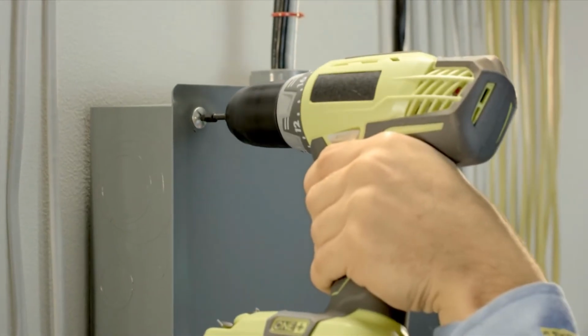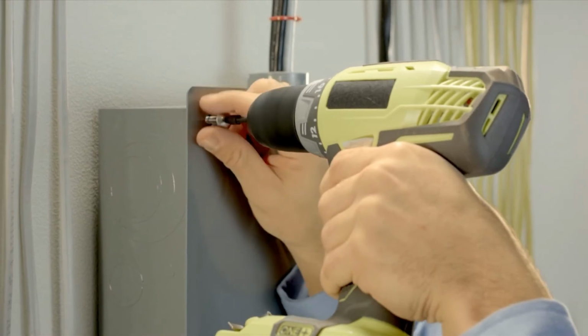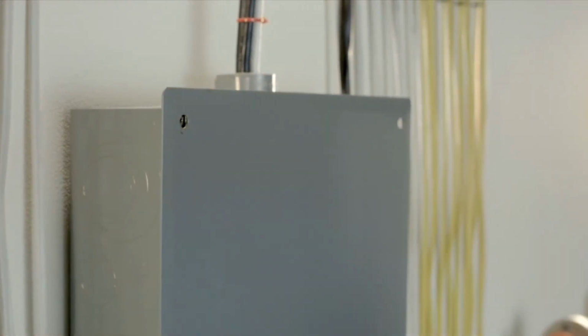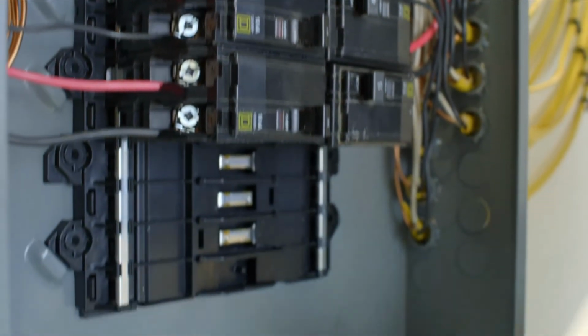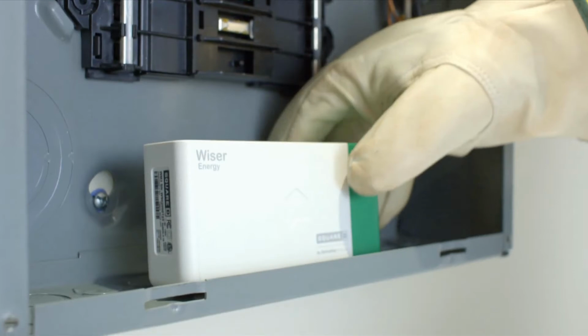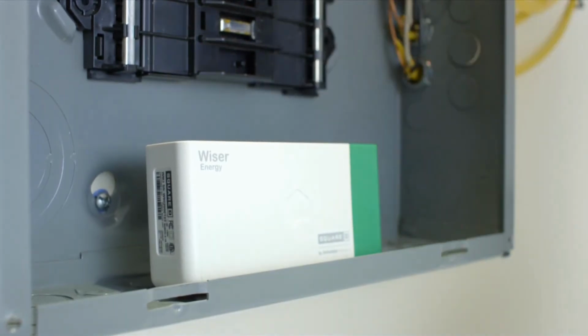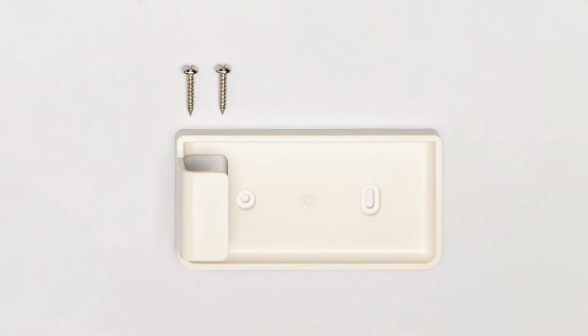To access the circuit breakers, you'll need to remove the screws on the electrical panel cover. Once the panel is open, find the best spot inside to place the Wiser Energy monitor. If there isn't room, the monitor can be mounted in an external enclosure following Canadian Electrical Code, provincial and local electrical and building standards. Next step is installing the antenna.